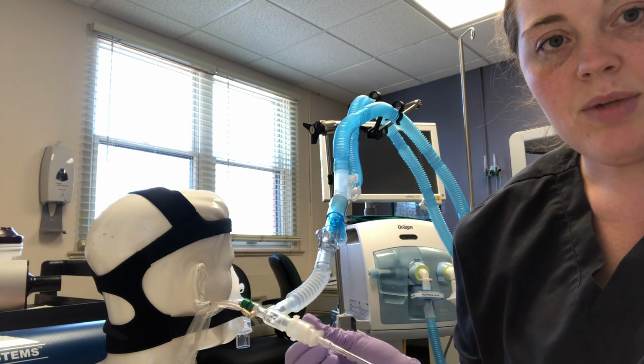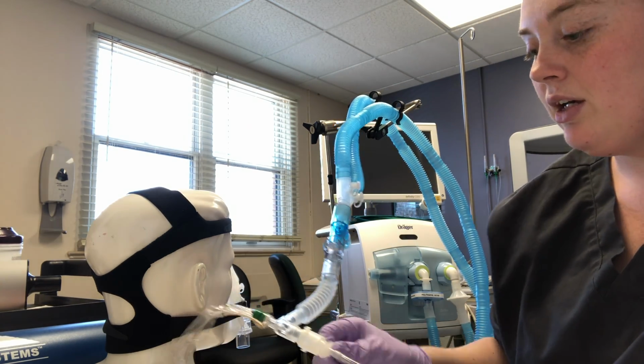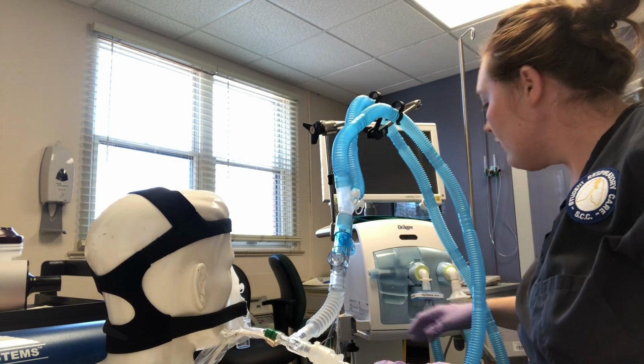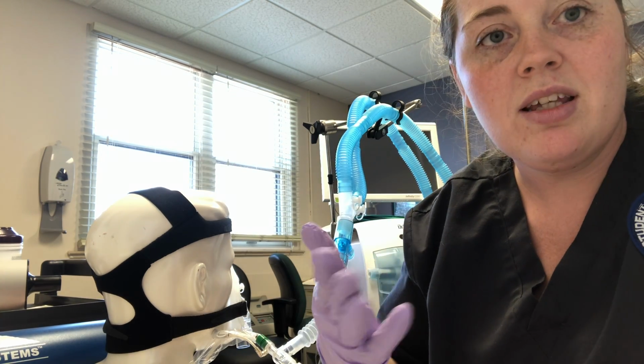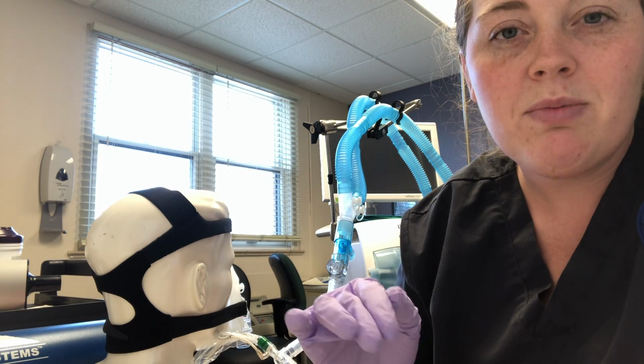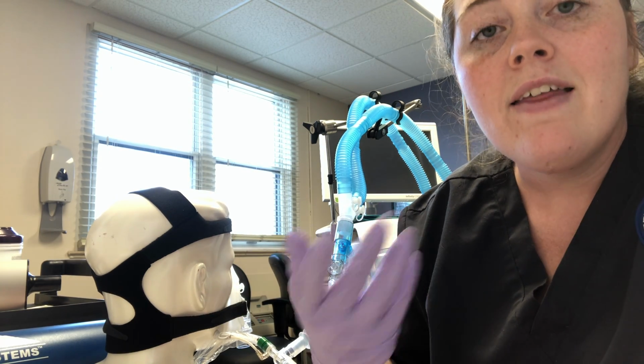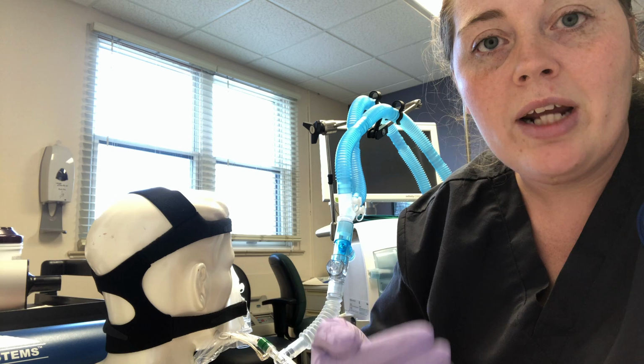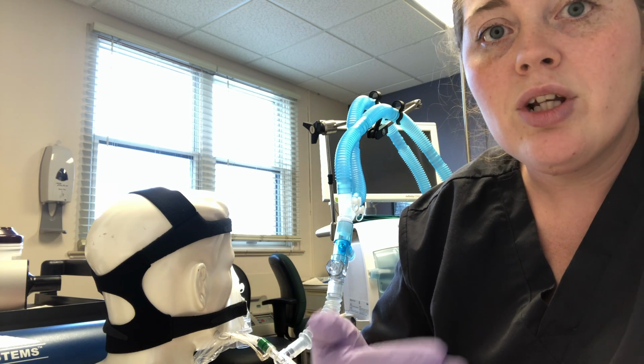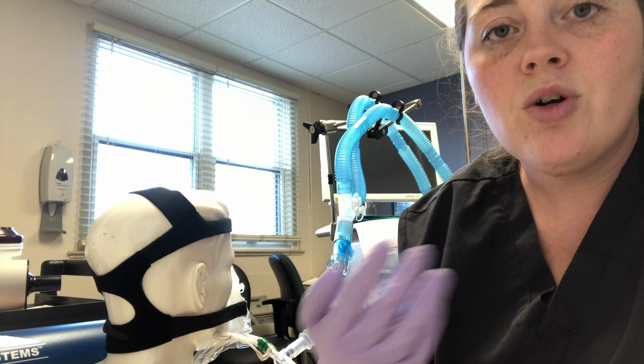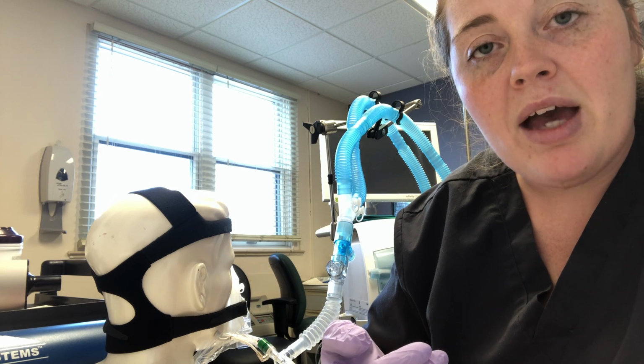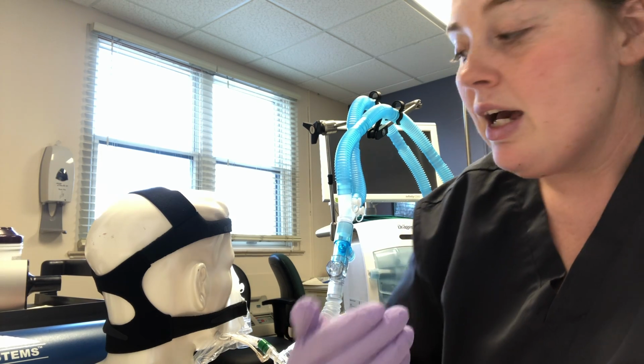So now I'm going to go ahead and set my parameters on this ventilator. So anytime you use the ventilator or the BiPAP, you do need to make sure that it's always plugged into the red outlet. That way it's hooked up to the backup generator should you have a power outage. These people need these devices, and so it's really important that we have a backup plan should we need one.